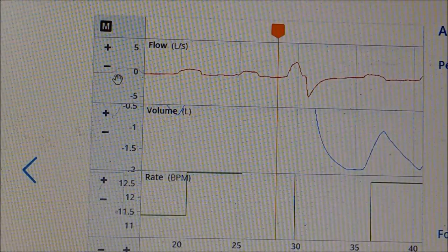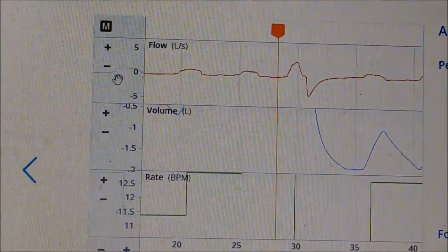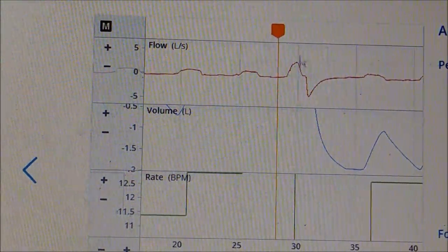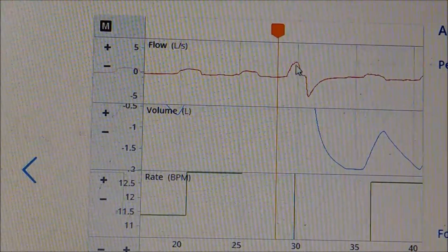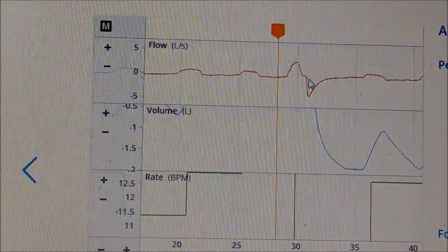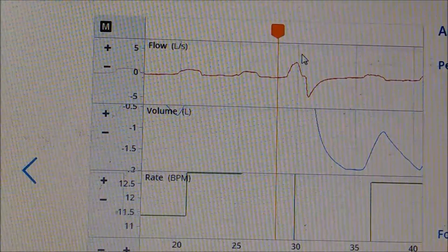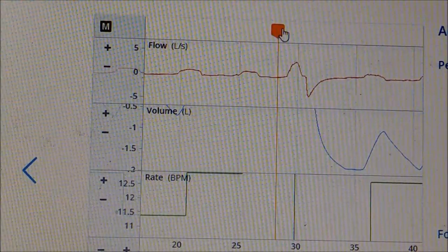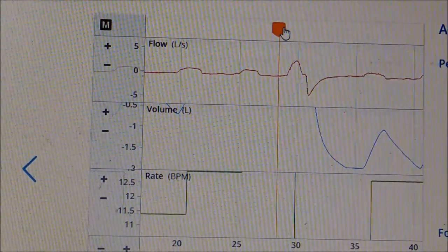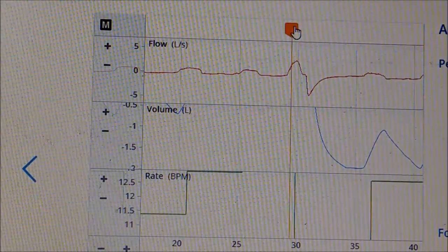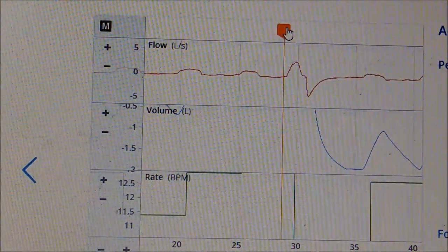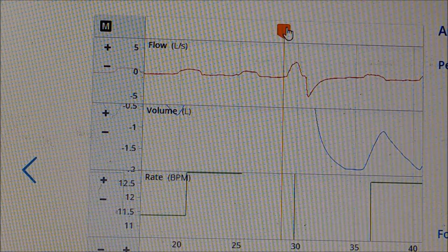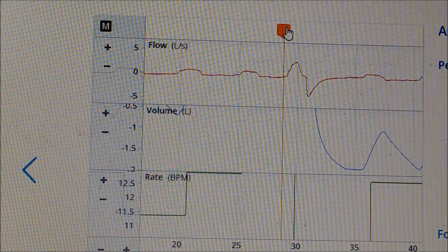So next, you'll want to adjust the scale on the left-hand side where that little hand icon is. We need to do this so that we can see the total peak and the total valley of that max inhalation and exhalation. From there, we can use the selector tool right there to get the actual value, so we can adjust that by holding on it and moving it around. This will give us the exact values so we can enter it into the table and do our calculations.